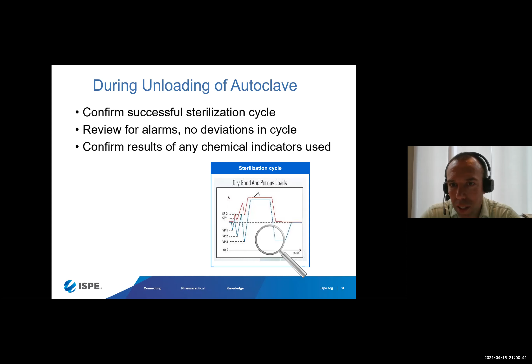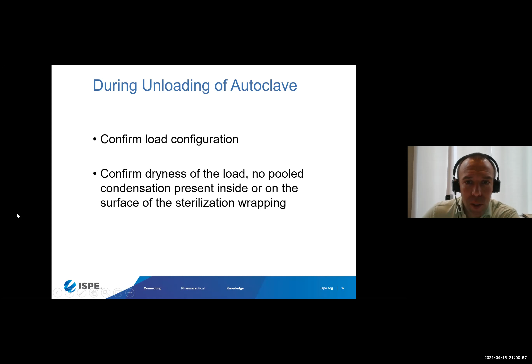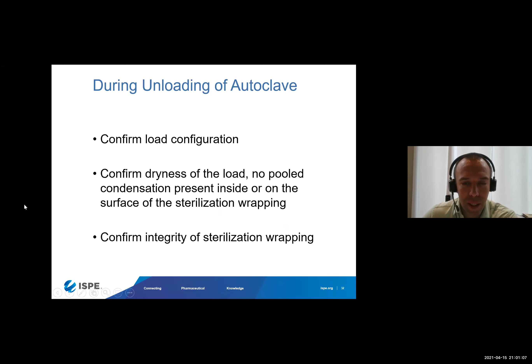We're also checking that the load configuration is according to the validation as documented in our procedures. We're checking for dryness of the load, no pooled condensation inside or on the surface of the sterilization wrapping, and also checking the integrity of the sterilization wrapping itself.